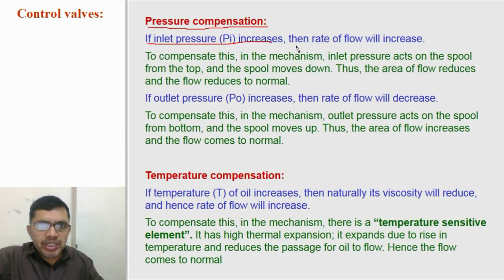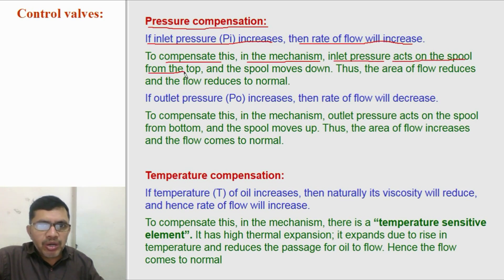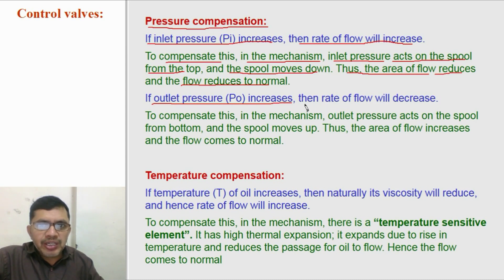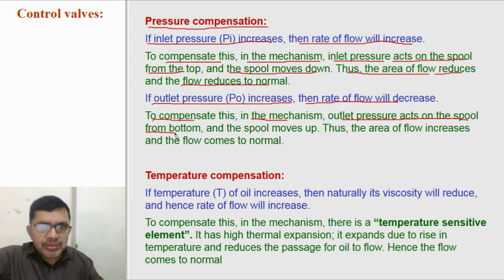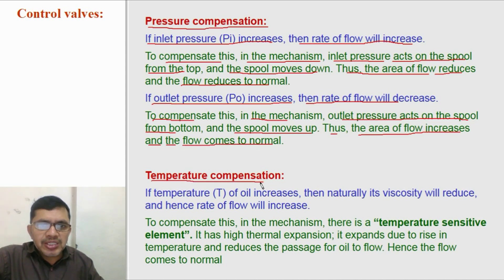If inlet pressure is more than the outlet pressure, then the rate of flow will be more. To compensate this, in the mechanism, inlet pressure acts on the spool from the top. The spool moves in the downward direction, thus the area of flow reduces and the flow will reduce to normal. If outlet pressure is more than the inlet pressure, then the rate of flow will reduce. To compensate this, in the mechanism, the outlet pressure acts on the spool from the bottom and the spool will move in the upward direction. Thus, the area of flow will increase to allow more oil and the flow becomes normal.